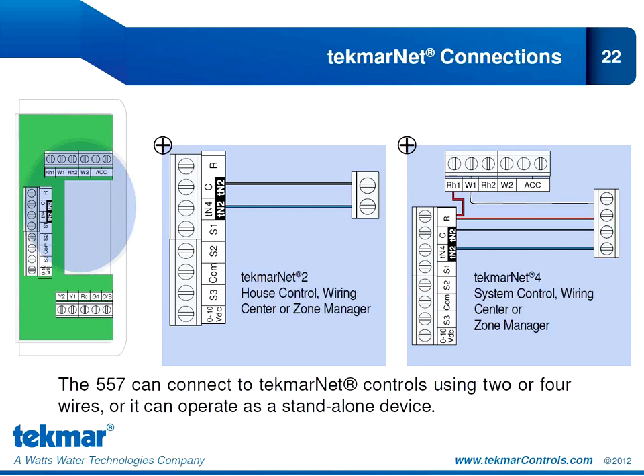tekmar has two lines of communicating controls: tekmarNet2 and tekmarNet4. In the past, thermostats were either TN2 or TN4. What's great about the 557 is that it can be both. You can configure it for a tekmarNet2 system with two wires connecting to a TN2 house control wiring center or zone manager, or connect it to a TN4 system control wiring center or zone manager. We can even use the 557 in standalone operation. It can be used for TN2, TN4, or standalone; for new construction or two-wire retrofits; connected to system controls, in a thermostat-only network, or as a single standalone thermostat. The choice is yours.